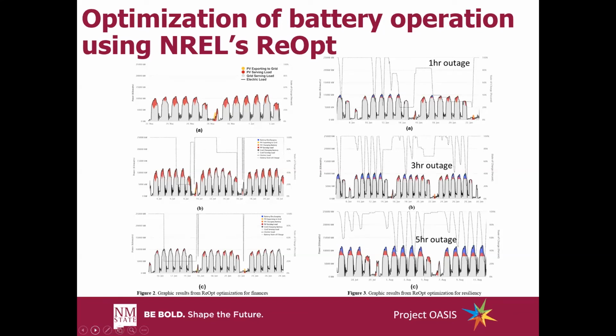The third limitation of Reopt was that the recommended battery usage was less than efficient, as you can see by the fact that dashed lines keep the battery's state of charge close to 100% with only a few discharges. It would be more optimal to keep the battery's state of charge within the range of 75 to 80%. This allows the battery to absorb PV overgeneration when a load of the university is low and charged directly from the PV, avoiding any exporting onto the grid. Choosing anything other than 100% SOC is not currently an available function in Reopt.